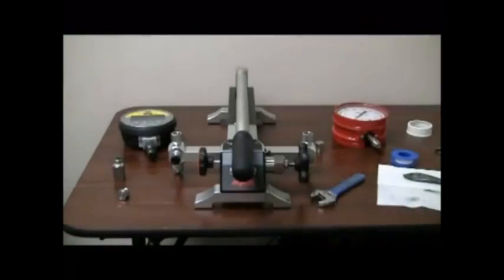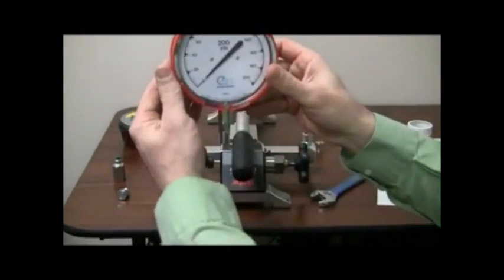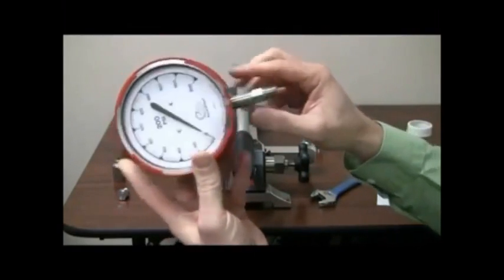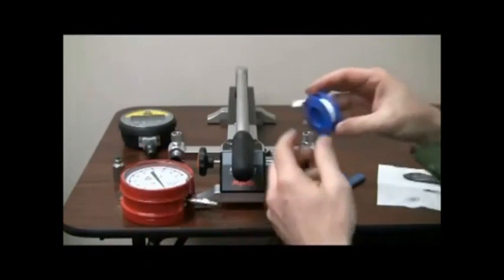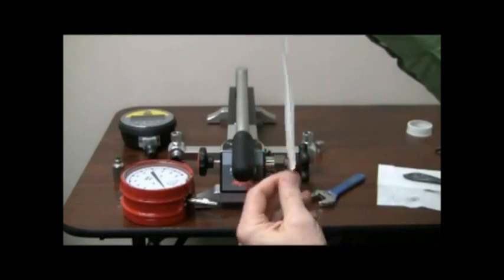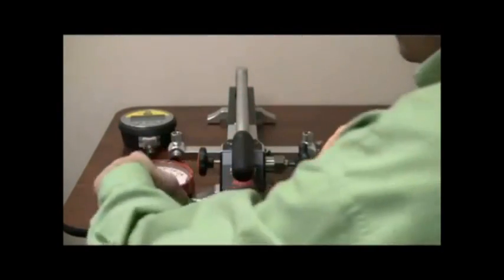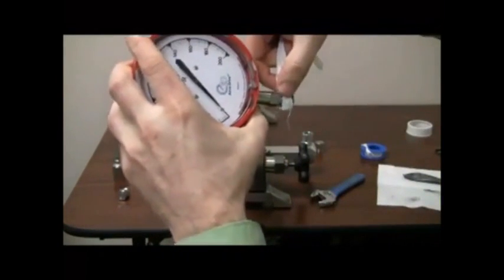Because we have stainless steel fittings, we're going to take some extra precautions on installing a gauge. Make sure the threads are clean. I'm going to unroll 6 inches of Teflon tape and wrap it in a clockwise direction around the fitting, ensuring a nice tight wrap.